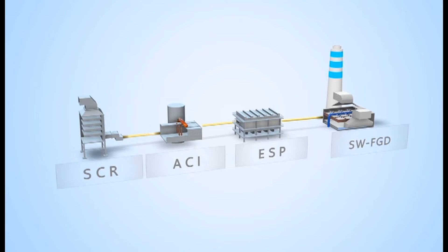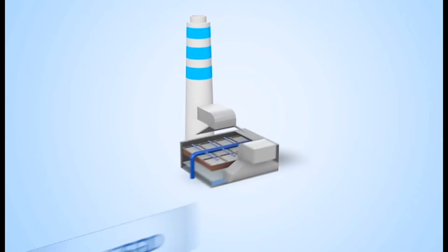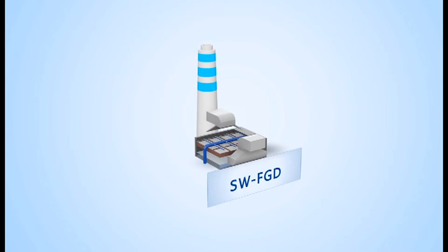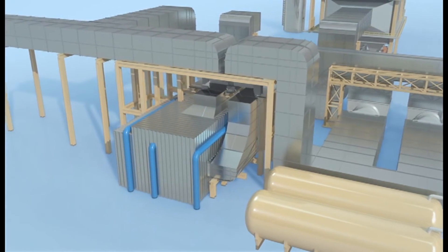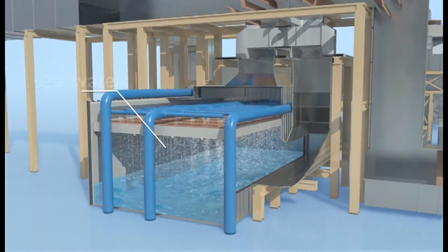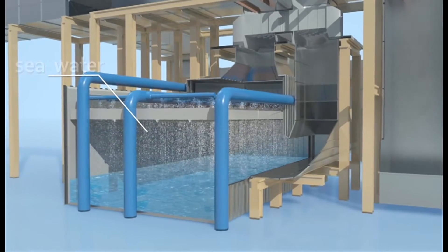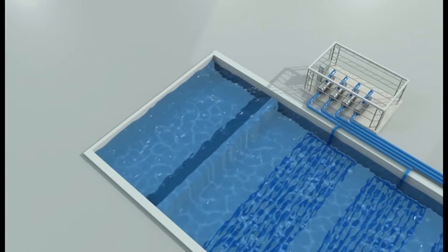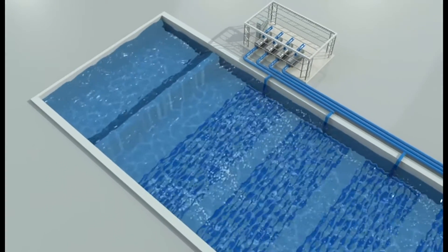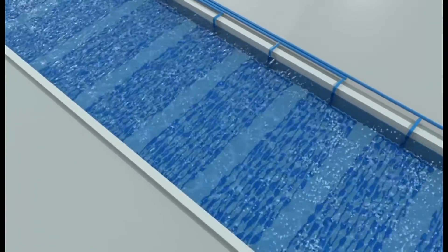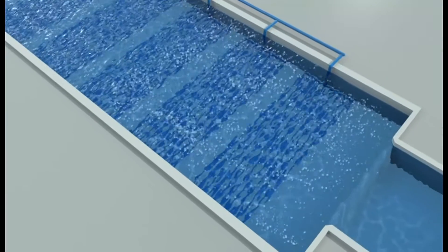Now we move on to sea water flue gas desulfurization, or sea water FGD. The process sprays the sea water, which is alkaline, to react with sulfur dioxide, which is acidic. The sea water will adjust the acidity to neutral. Then, it will flow to the aerated lagoon to add oxygen back. After this process, sulfur dioxide turns into sulfate, which is an element of natural sea water.